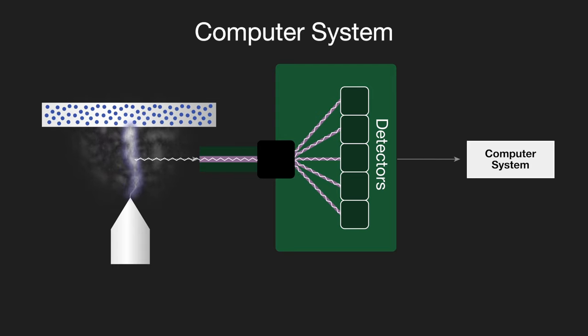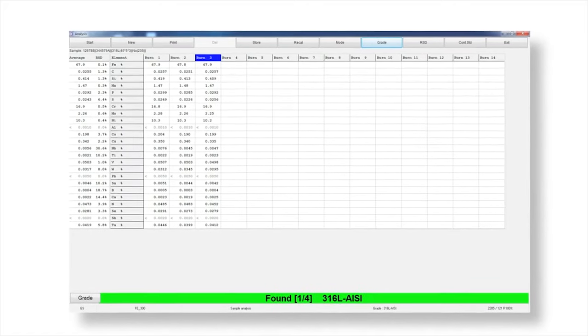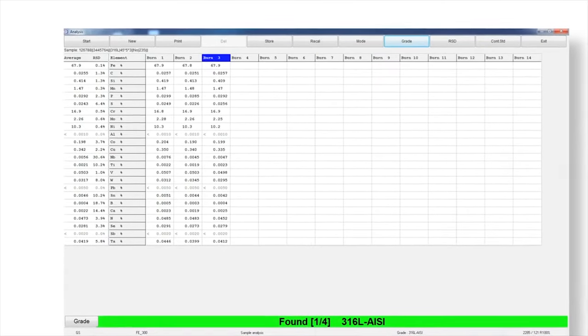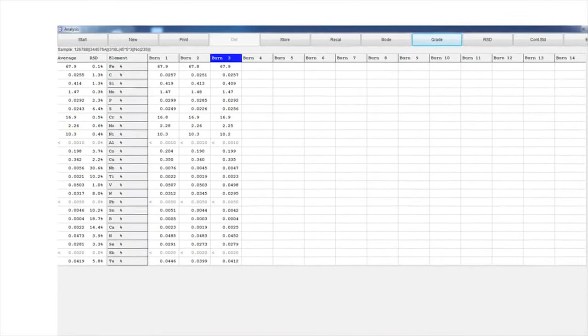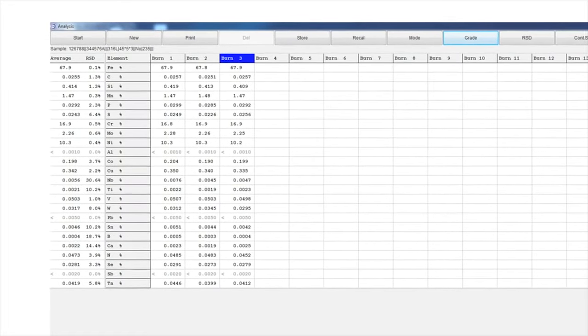The third component is the computer system. The computer system acquires the measured intensities and processes this data via a predefined line calibration to produce elemental concentrations. The user interface ensures minimal operator intervention with results clearly displayed, which can be printed or stored for future reference.